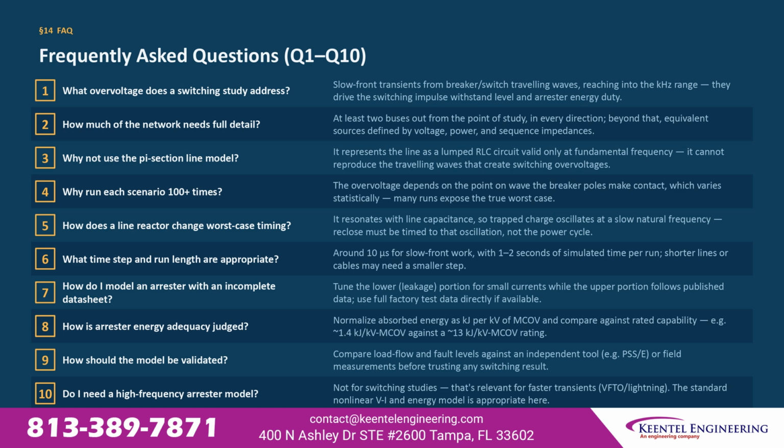How should the model be validated before use? Compare load flow and fault levels against an independent tool such as PSCAD or against field measurements before running any switching scenarios. Is a high-frequency arrestor model needed for switching studies? No. High-frequency models are relevant for very fast transients and lightning. The standard nonlinear VI and energy model is appropriate for slow front switching work.